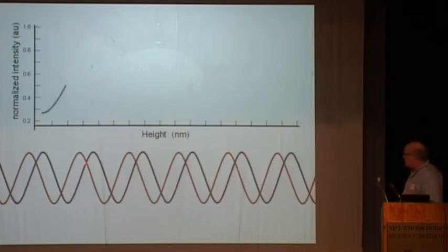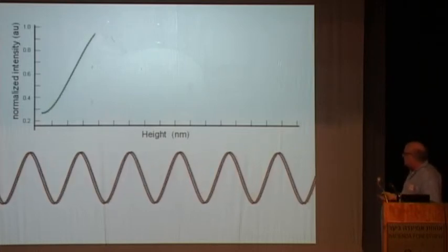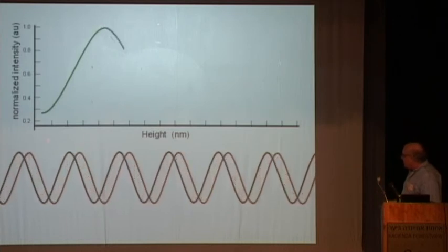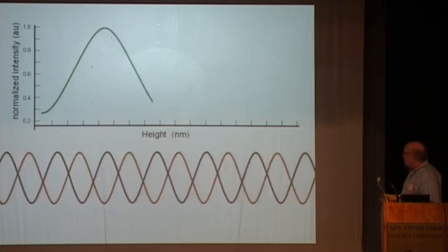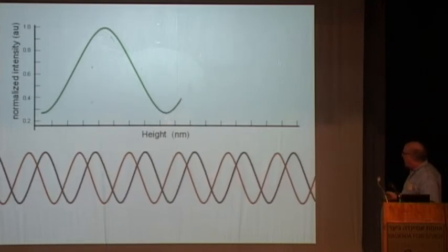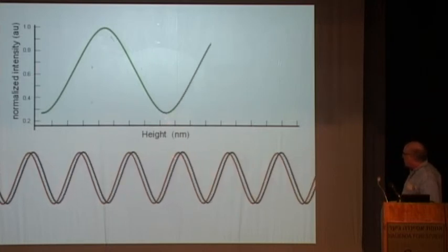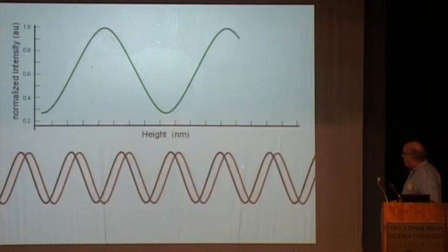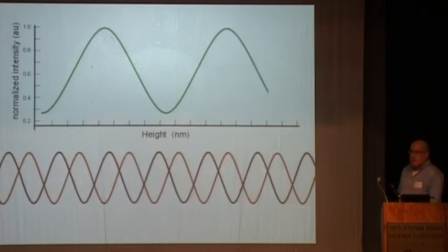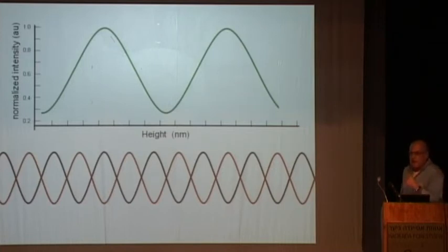And so again, as this is being delayed, we see an increase in signal, but once it passes the peak, then it goes down to the lowest level, and then back up as we approach the constructive, and ultimately down to maximal destructive interference. And so through that, in essence, what we have is an oscillation in the intensity per each pixel that we're measuring, and that is going to give us the information and the ability to calculate what is the added height at each feature that we've immobilized to the surface of the chip.